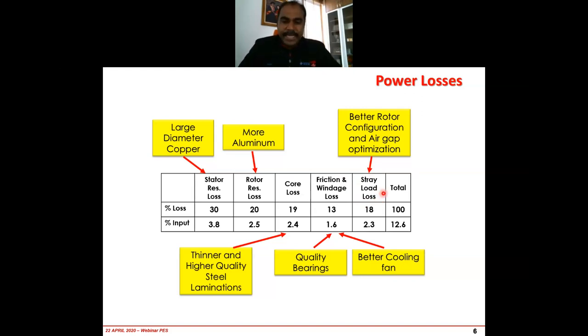So the existing induction motor, they optimize it. How do they optimize? For instance, to reduce the stator resistance losses at the winding, they use a large diameter copper as the winding coil. Similarly, more aluminium at the rotor. All this will minimize the resistance and therefore reduce the losses. For the core loss, of course, they use better quality laminated steel to minimize the core loss. Similarly, better quality bearings and a better cooling fan reduce the friction and windage losses. Similarly, they optimize the air gap to reduce the stray load losses.